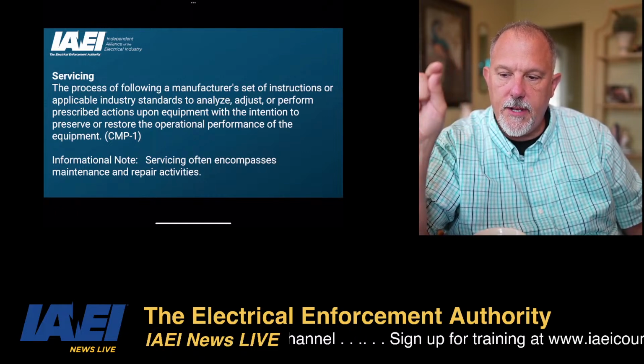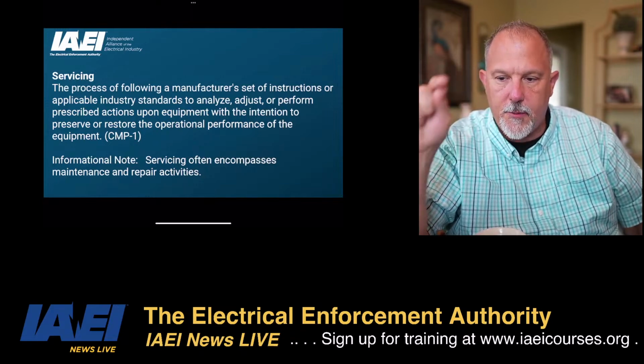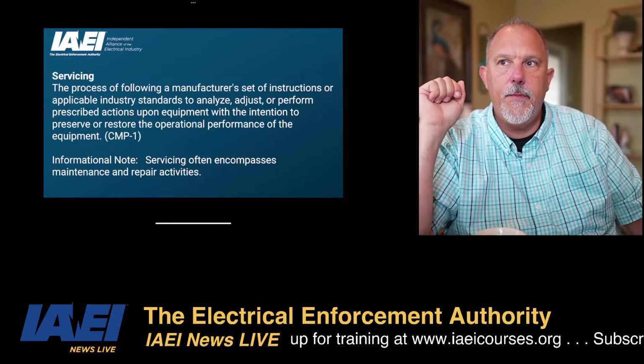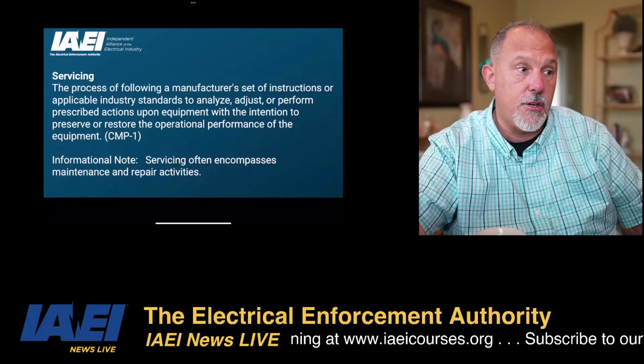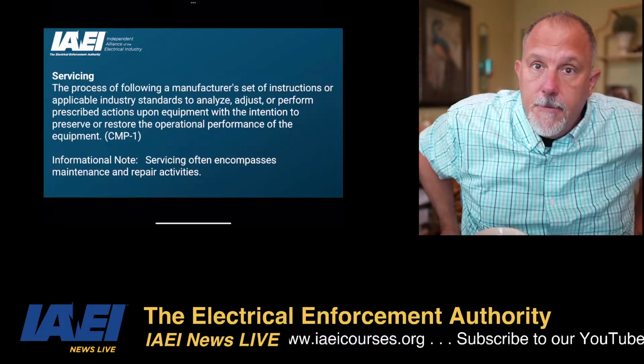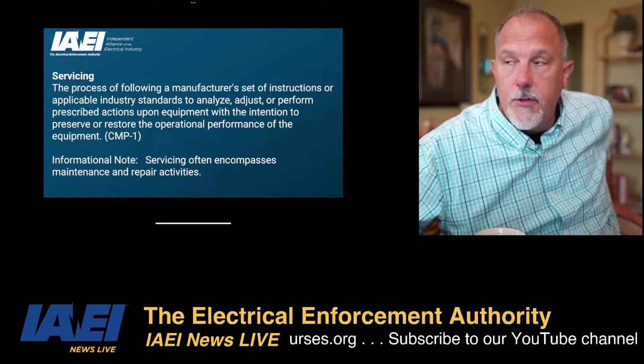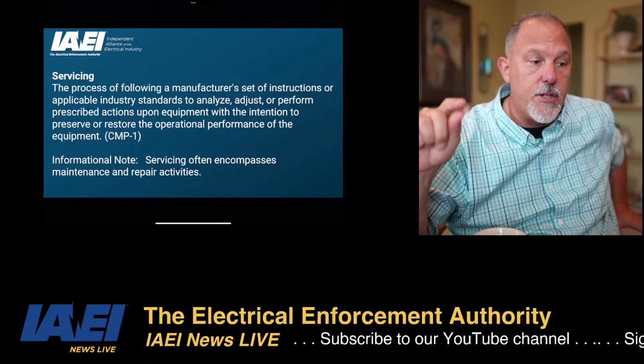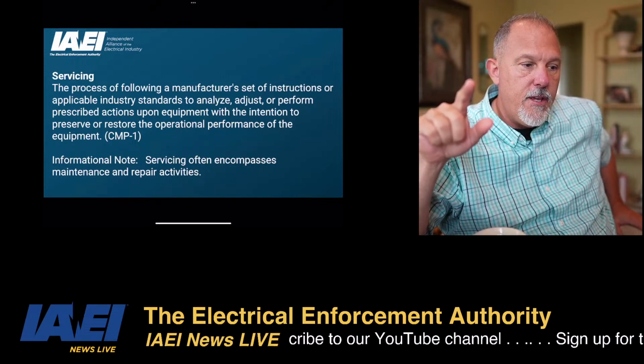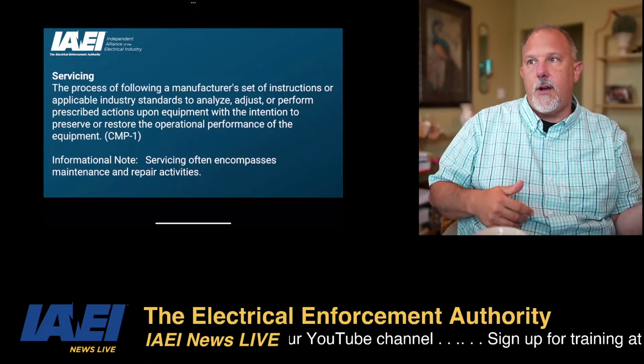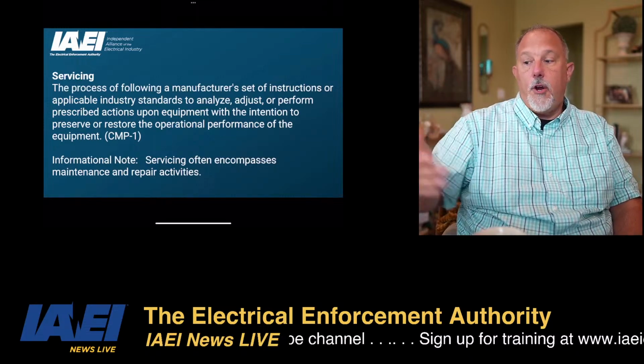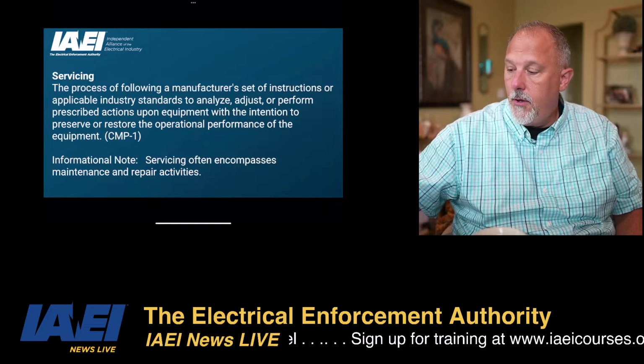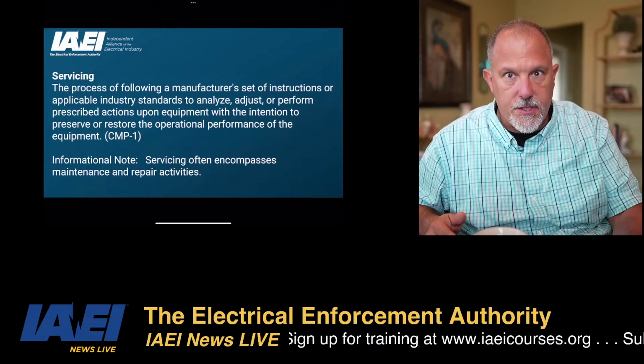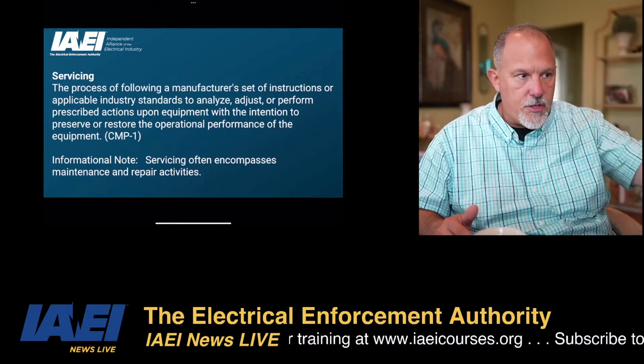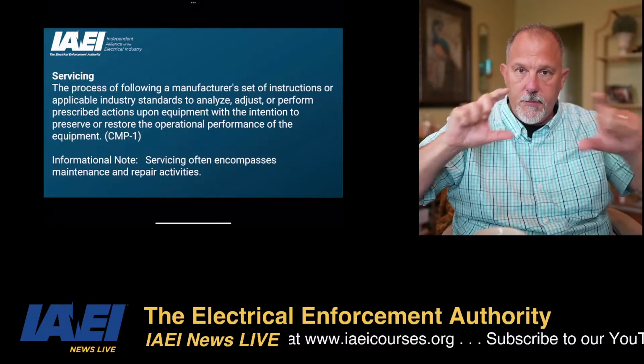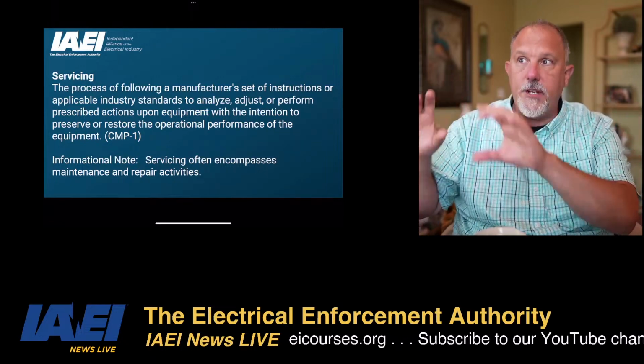Exercising the circuit breaker would be under maintenance if the manufacturer says so—yes, Steve Cavaleris, I agree with you 100%. Exercising a circuit breaker and doing all of those things, I'd say, is servicing, not maintenance. And I wouldn't use the word repair anywhere in the code either. I made a bunch of public inputs to fix that issue, because if you say repair, are you talking servicing, or are you permitting reconditioning, or just servicing? Since we have defined terms—servicing and reconditioning—we need to keep those two distinctive and use the right terms in the right places.